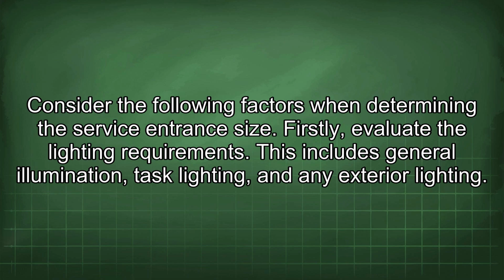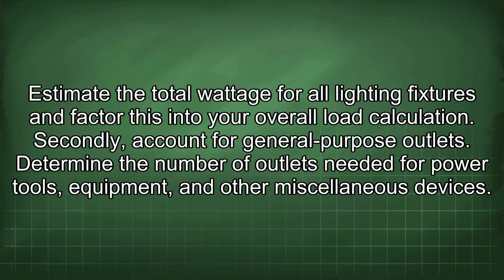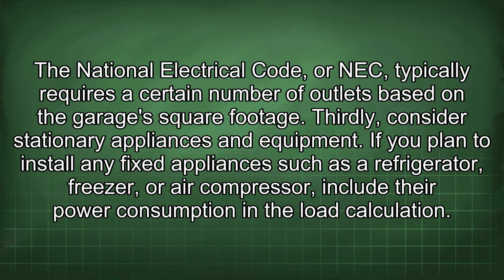Firstly, evaluate the lighting requirements. This includes general illumination, task lighting, and any exterior lighting. Estimate the total wattage for all lighting fixtures and factor this into your overall load calculation. Secondly, account for general purpose outlets. Determine the number of outlets needed for power tools, equipment, and other miscellaneous devices. The National Electrical Code, or NEC, typically requires a certain number of outlets based on the garage square footage.